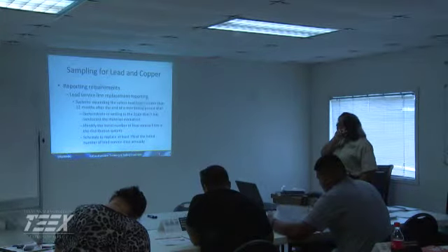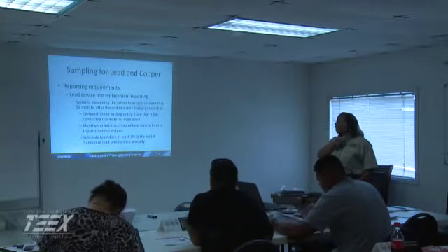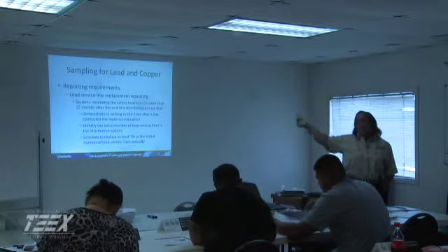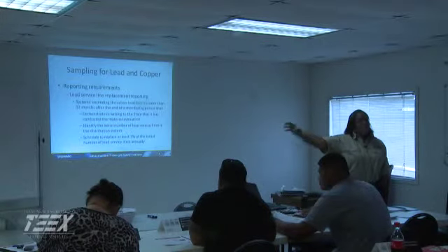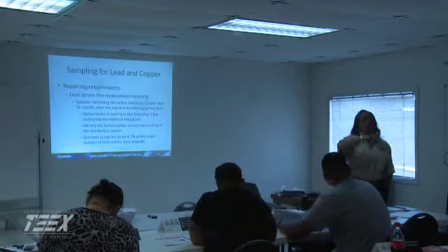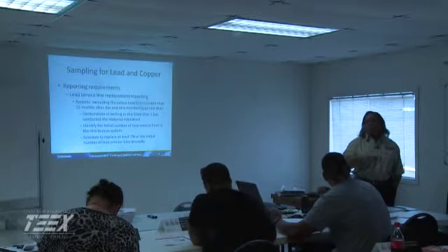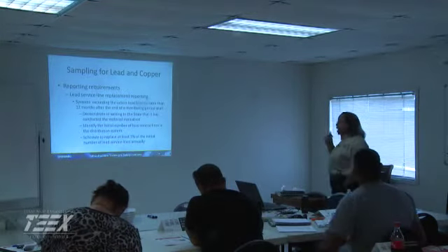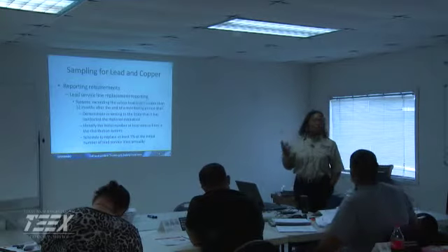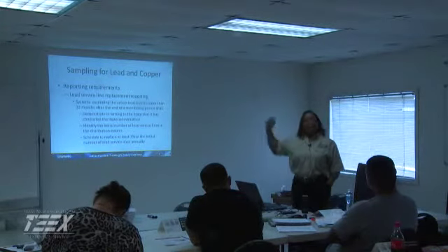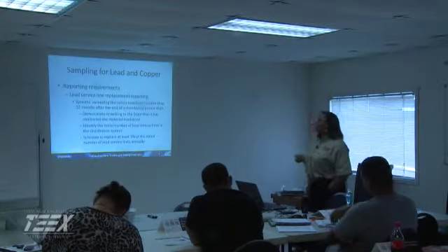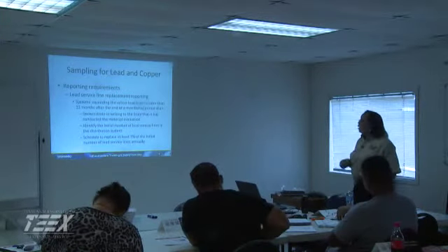With your lead service line replacement, keep in mind that I told you initially when the law went into effect, EPA says that if you had a problem, you had to physically remove or replace 7% of your lead service lines on a minimum of an annual basis. And you've got to make sure that you're documenting and reporting that back to the state or EPA also.